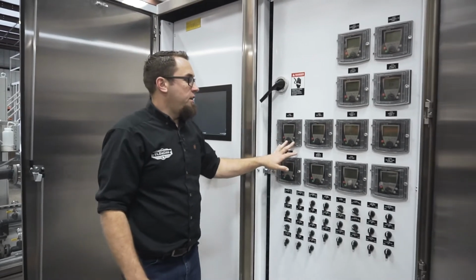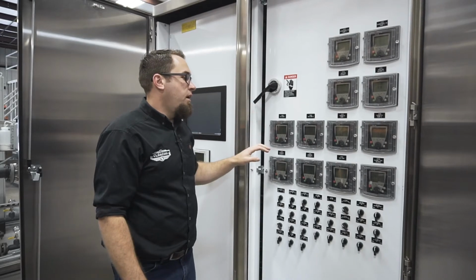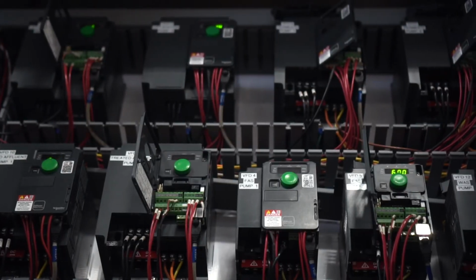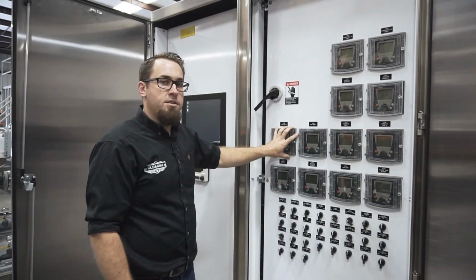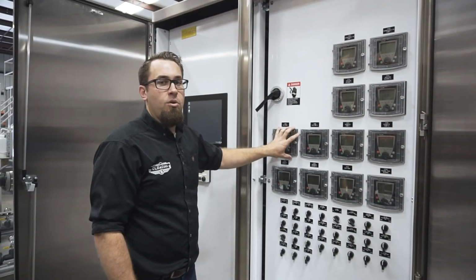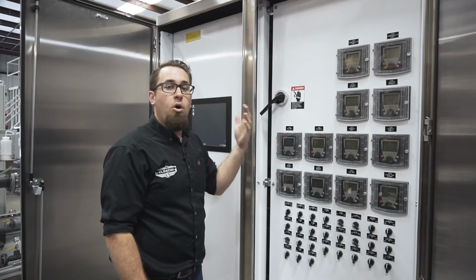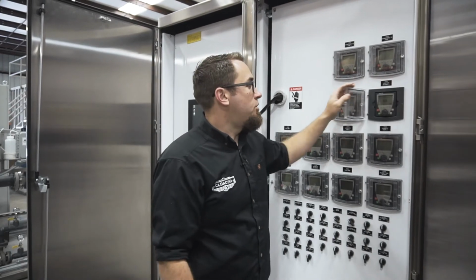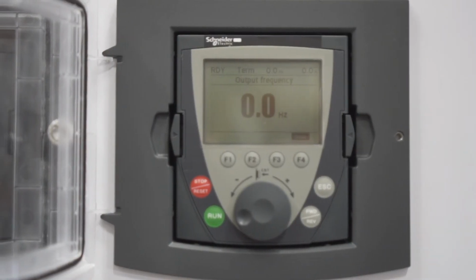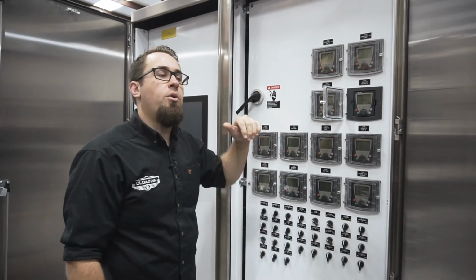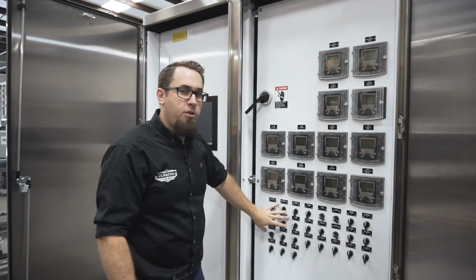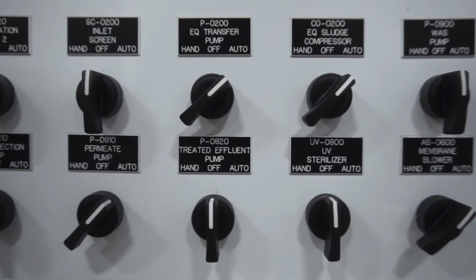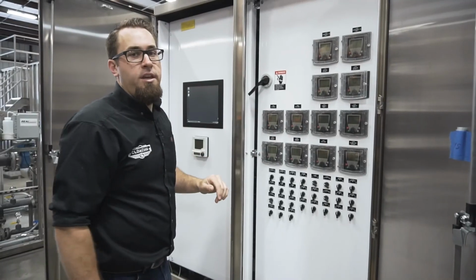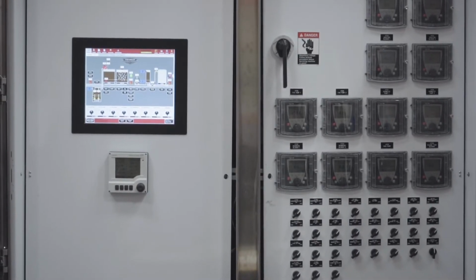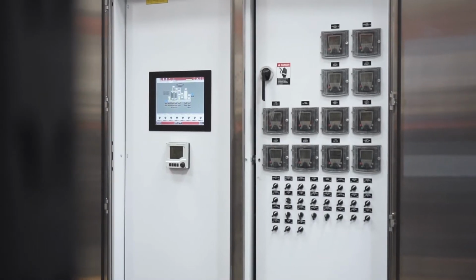Next up, you have the VFDs. You'll notice there are many VFDs inside of this panel, and with normal configurations, the VFDs are only accessible on the back side of the inner door. One of the things that we started to do years ago was provide remote interfaces for all of the VFDs on the inside of the inner door, so that in the event that you have a VFD failure or even a momentary blip, it allows you to go in and immediately reset. You can just simply go in here, configure or toggle through all of the screens, immediately reset it, and you don't have to have an electrician go in behind the inner door. You have all of your HOA switches out on the front, but it also allows you to close the doors and lock them, and all of them come with keys so that you can limit the access to whoever has that set of keys.